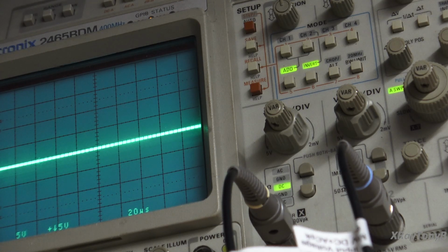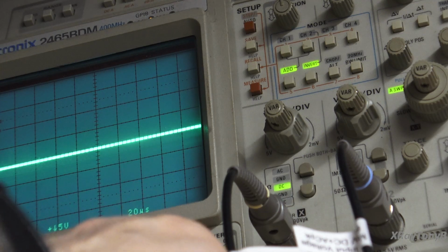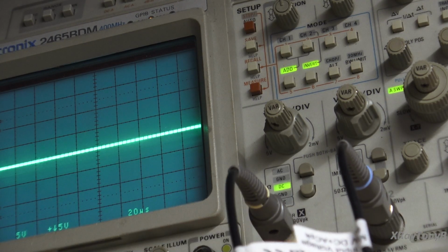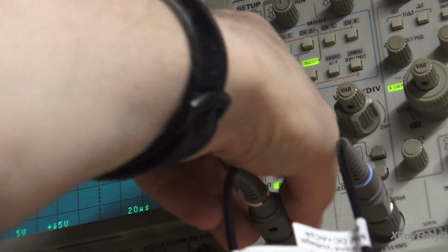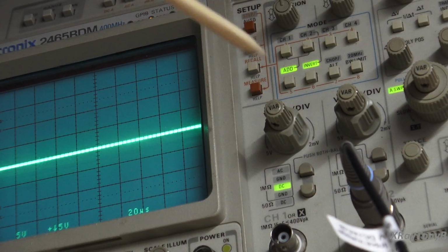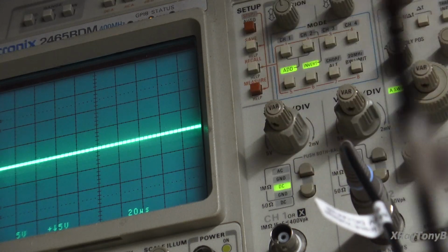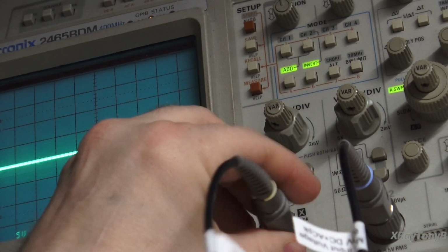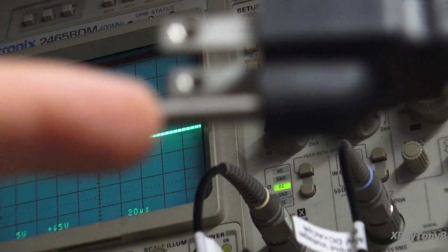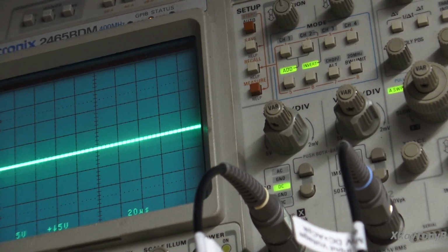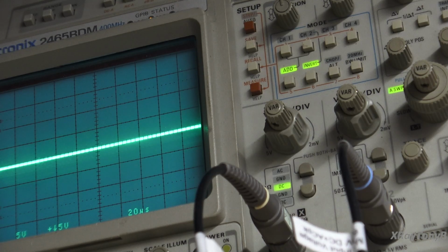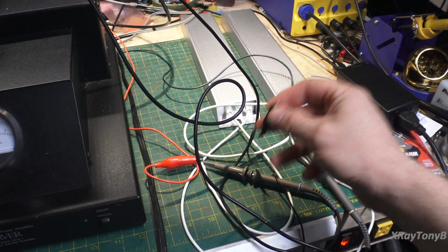This is called differential mode because it's looking at the differential voltage between these two tips of these two probes. The reason this is important is we are not connecting anything electrically to the outside, the grounded part of the probe. As we talked about in our little oscilloscope tutorial, the outer ring of your BNC connector for your probe port is physically connected to the ground prong of your cord. So if you look at the power cord here, this ground prong is connected to those jacks on the outer ring. What that also means is anything connected to this ground probe is also going to be connected to ground.